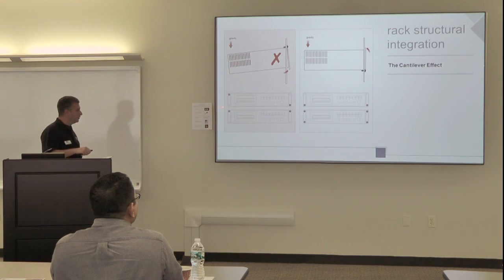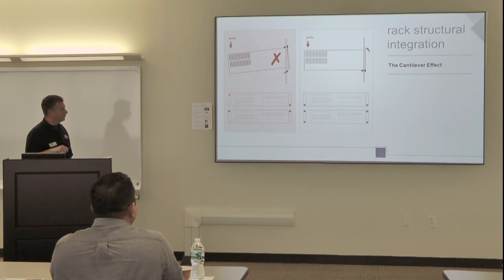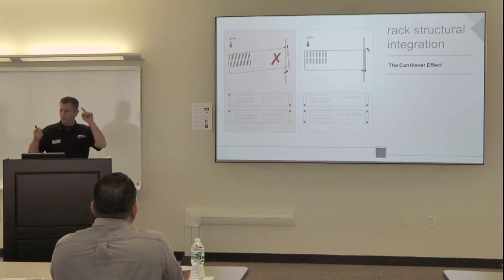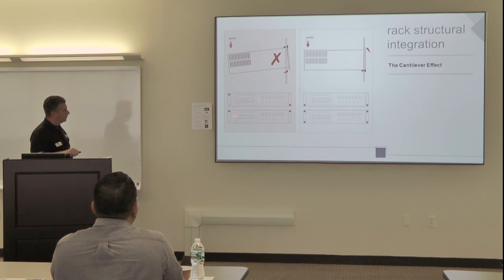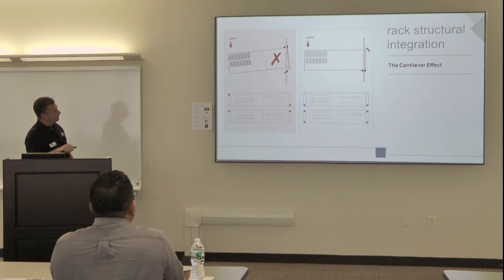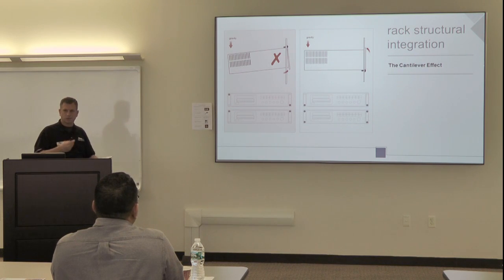Let's talk about the cantilever effect a little bit. I've seen this a lot out in the field, where people think they're saving time by only putting in 2 rack screws instead of 4, caddy-cornered like this. What that does is twist the unit. It's not a good way to do it, because when the weight is pulling, it's going to bend the face or ear of the component. If you want to put in 2 rack screws quickly to check that everything looks good, put them both at the bottom, then come back around and make sure all 4 rack screws are in. There are 4 screw holes for a reason—use them, so you avoid flex or bending.